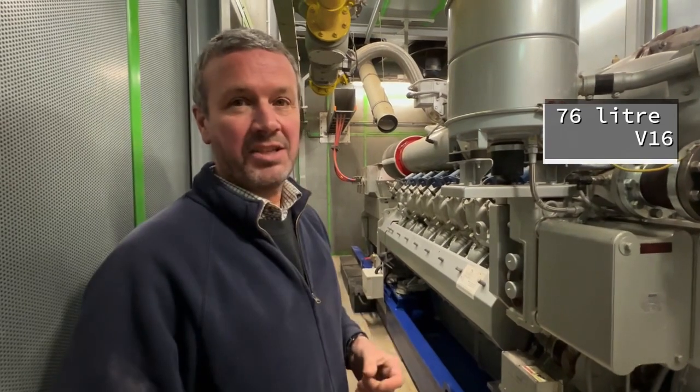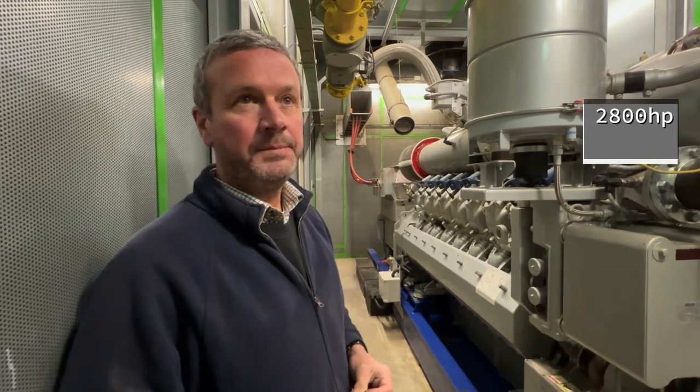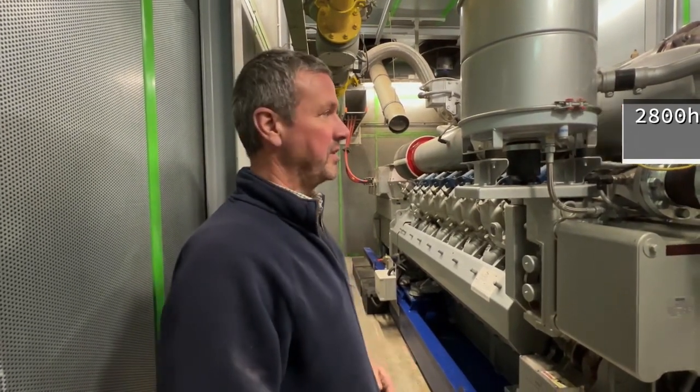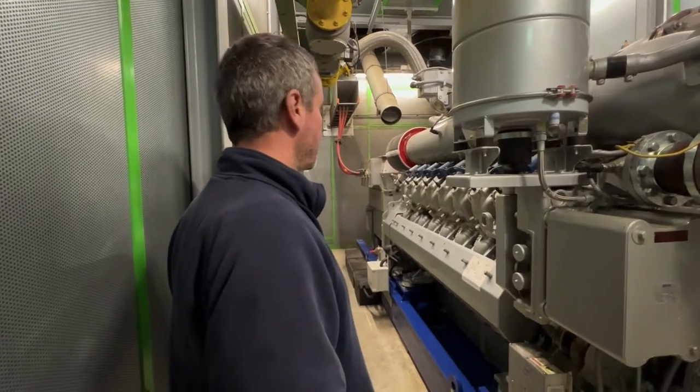It's a 76-litre V16, brilliant - 2800 horsepower at 1500 RPM, and it produces two megawatts of electric. There's a two-megawatt generator on the back, running at 11000 volts - so 2000 kilowatts.